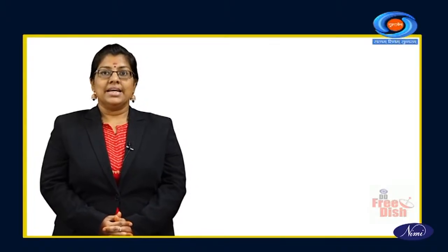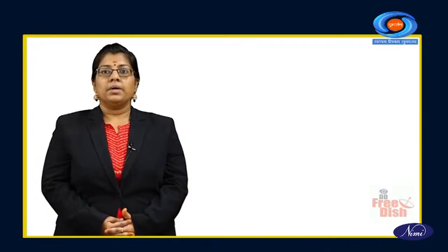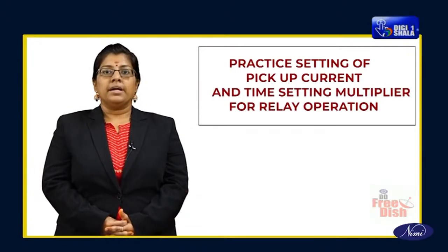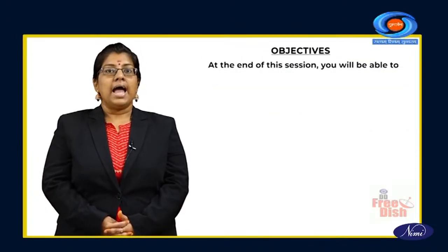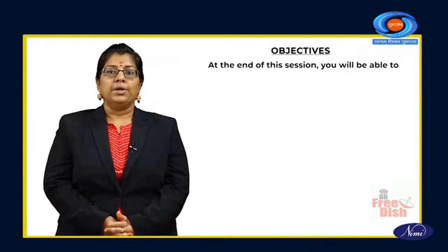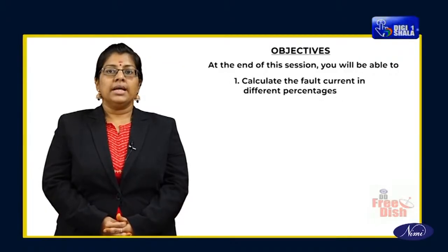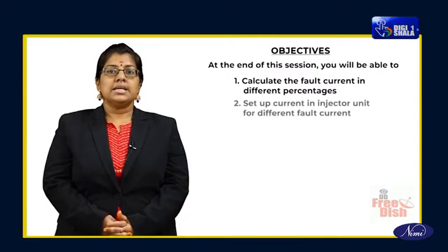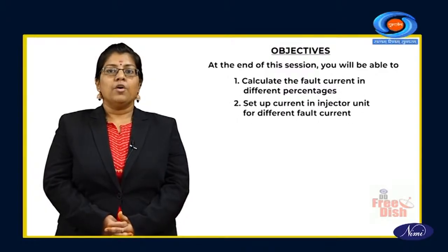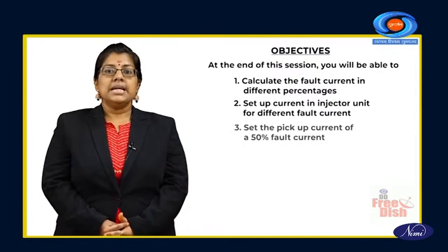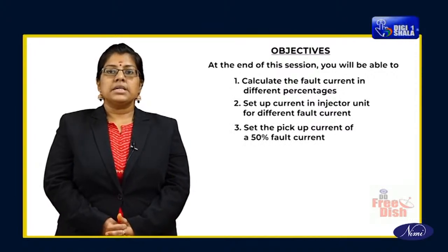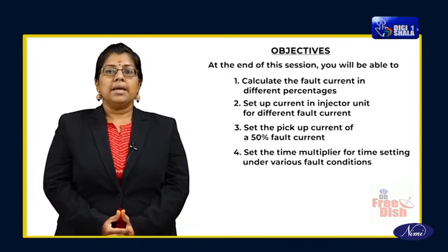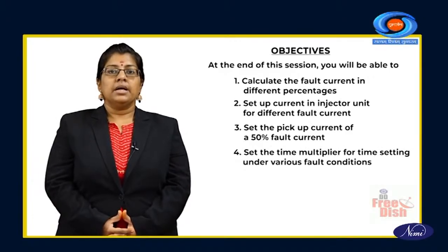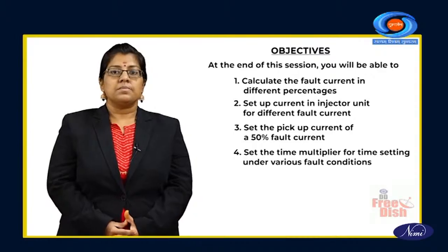A warm welcome to this session of Electrician Trade. In this session, we will learn about practice setting of pickup current and time setting multiplier for relay operation. At the end of this session, you will be able to calculate the fault current in different percentages, set up current in the injector unit for different fault currents, set the pickup current at 50% fault current, and set the time multiplier for time setting under various fault conditions.